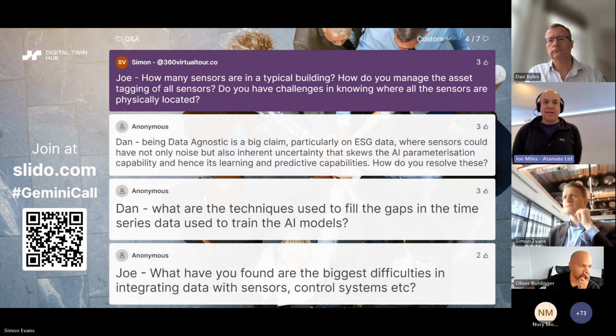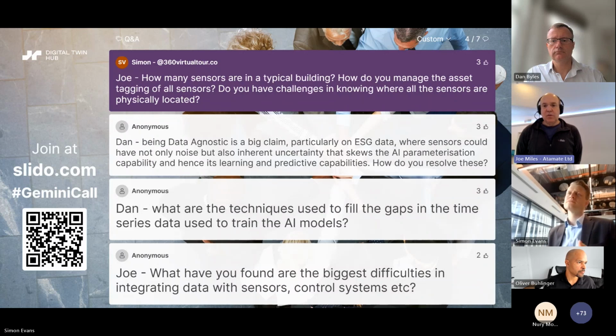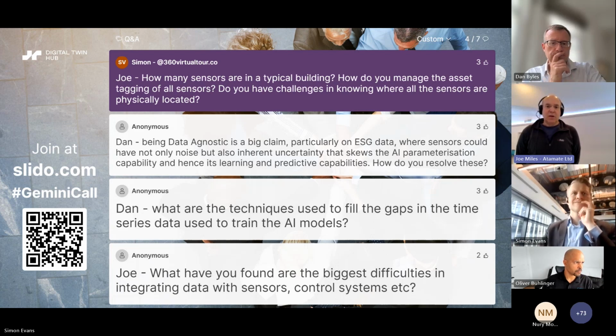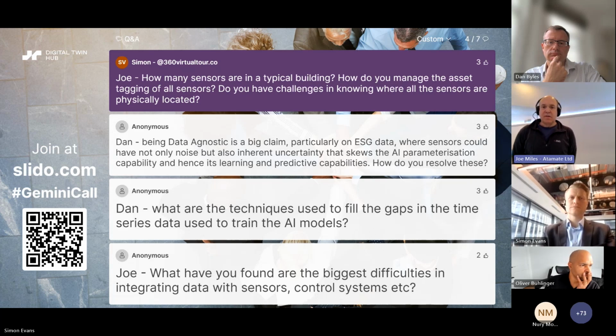As for how we manage the tagging of all the sensors—we don't tag them, because we have our own no-code design tool for the whole BMS system. Before installation, we design the whole system, and then we have a common config file that goes onto both the edge computers, our hub computers, and the cloud. So all the data is totally unified, and we know exactly what it all is. There's no manual tagging on any of the buildings—tagging isn't really a word we use, because we know the addresses of all the systems we're putting in. Do we have a challenge knowing where the sensors are? No, because we've designed the system.